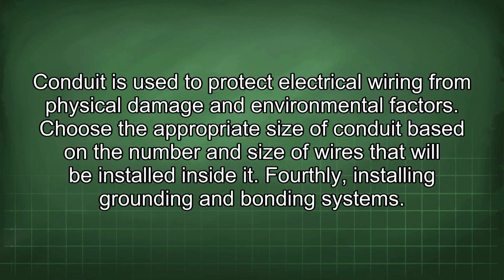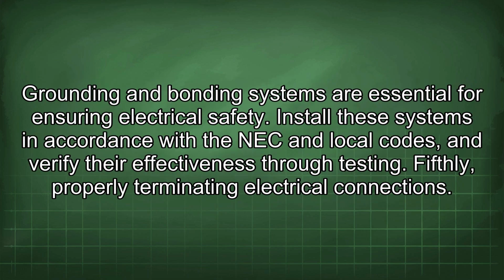Conduit is used to protect electrical wiring from physical damage and environmental factors. Choose the appropriate size of conduit based on the number and size of wires that will be installed inside it. Fourthly, installing grounding and bonding systems. Grounding and bonding systems are essential for ensuring electrical safety. Install these systems in accordance with the NEC and local codes, and verify their effectiveness through testing.